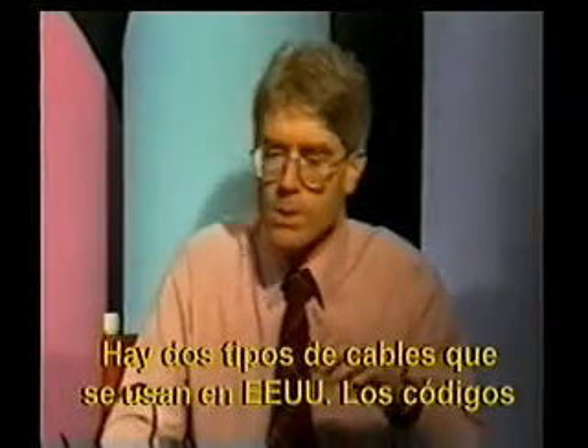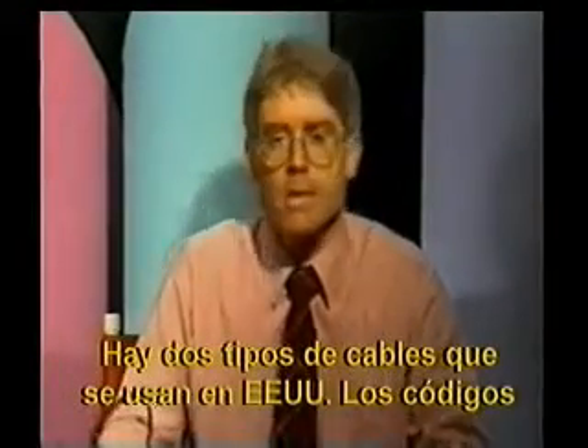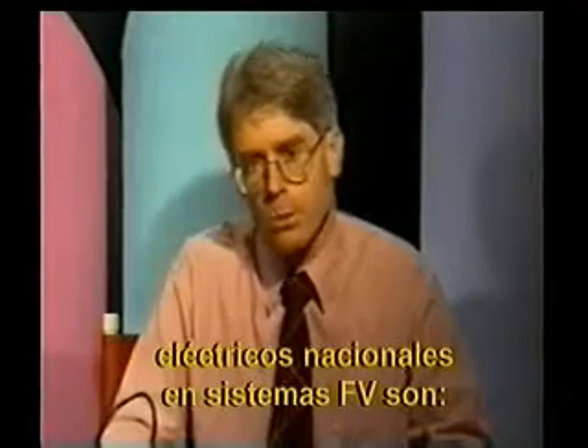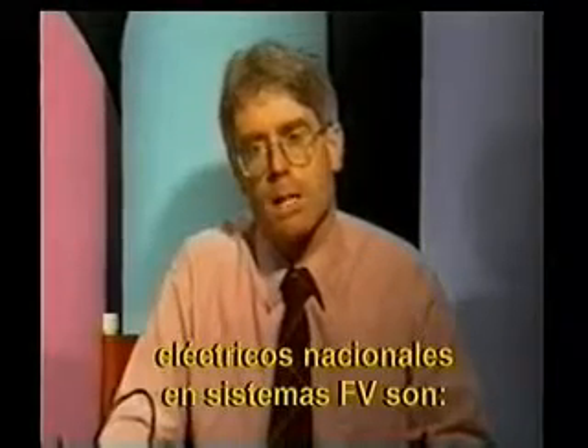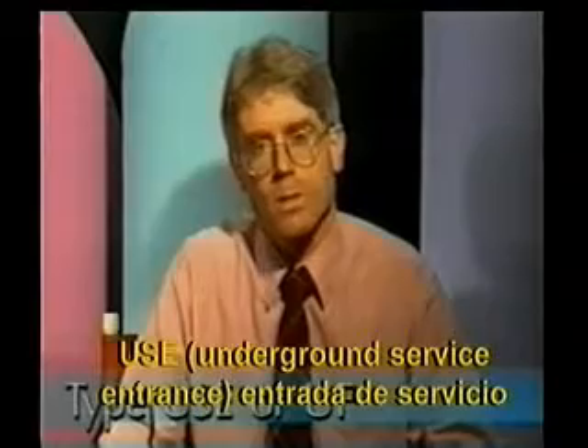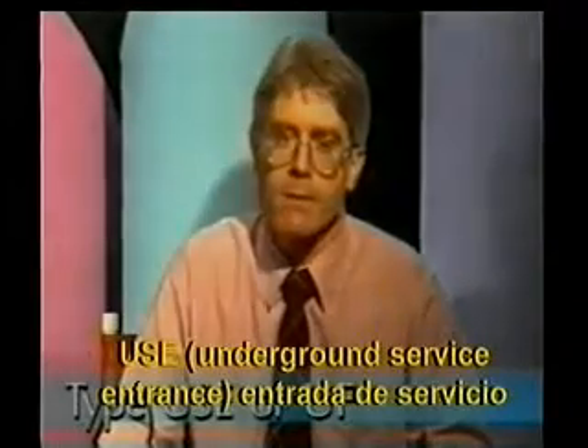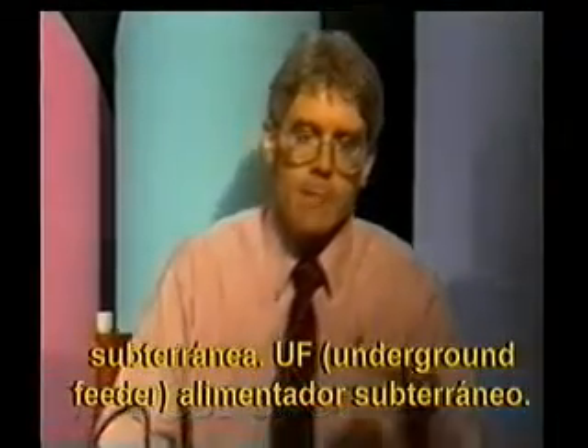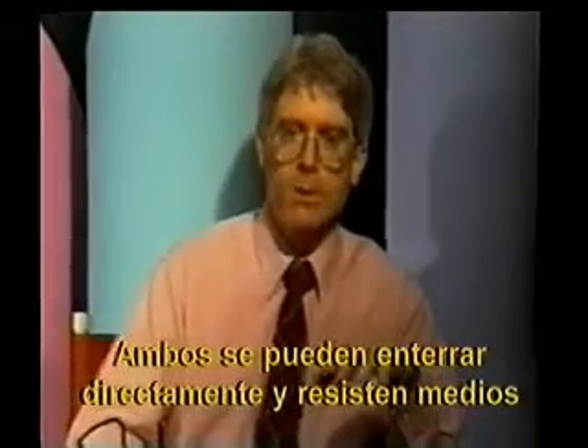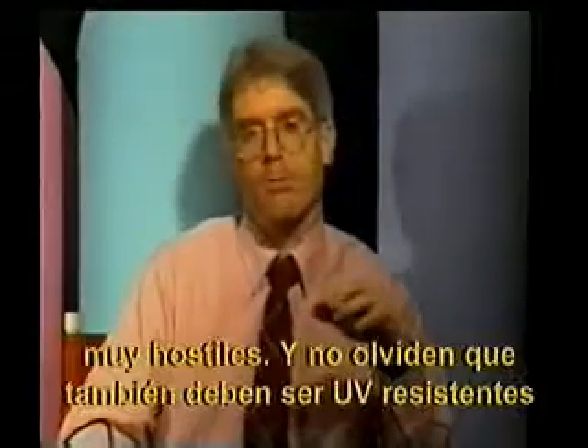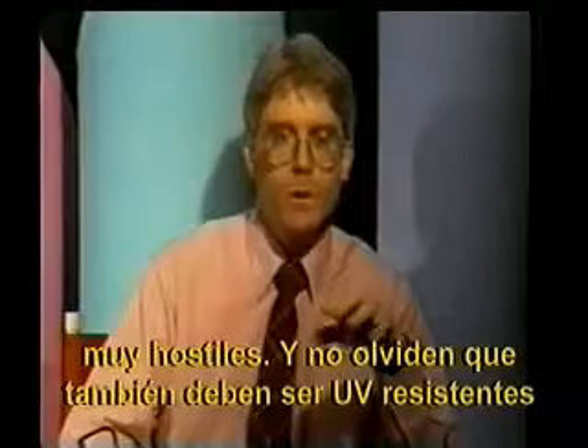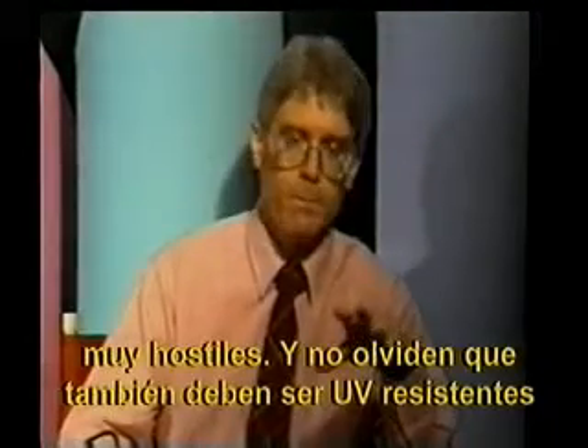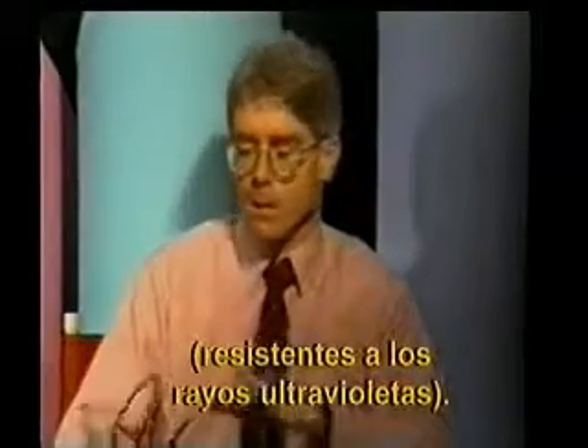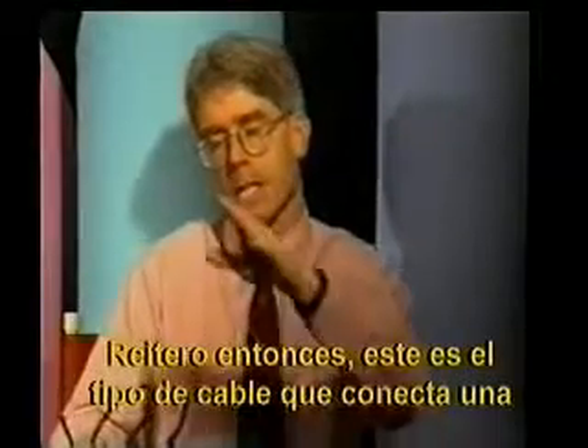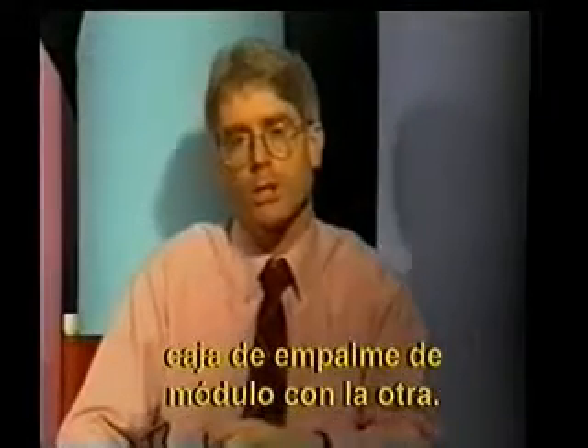Two types of wires that are specifically called out in the U.S. National Electric Code for use in photovoltaic systems are type USE, underground service entrance, and type UF, underground feeder. Both of those are direct burial types of wire. They can withstand very harsh environments. And you should also get these wires sunlight resistant, UV resistant. So once again, this would be the kind of wire that actually connects module junction box to module junction box.